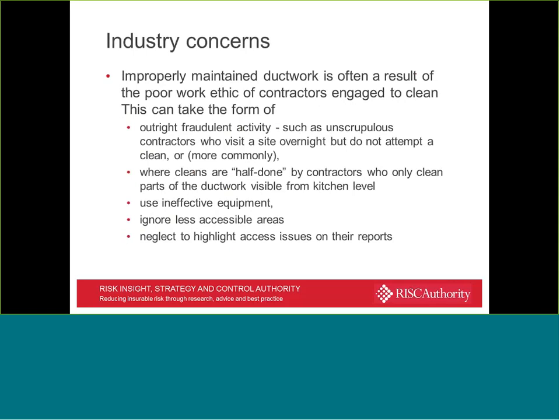As I mentioned, things have moved on a little bit over time. A few years ago, the Risk Control Working Group was made aware of some industry research that had been undertaken, not necessarily by insurers directly, but by a large property owner. And the results of that research highlighted a number of concerns: that improperly maintained ductwork was seen to be often a result of a poor work ethic of contractors engaged to undertake the cleaning work. This could take the form of fraudulent activity, contractors who just don't do the work, or alternatively don't do the work fully or properly, provide no evidence that the system has been effectively cleaned, use inefficient or ineffective equipment and cleaning methods, or ignore areas that are slightly more difficult to reach.